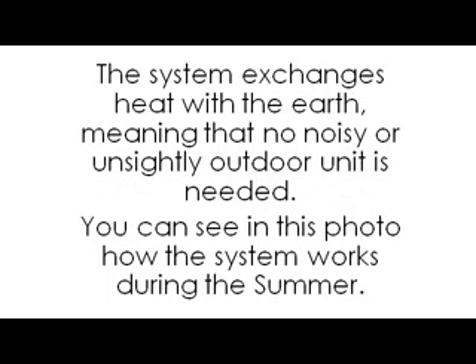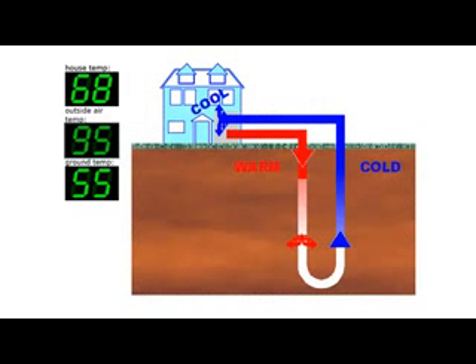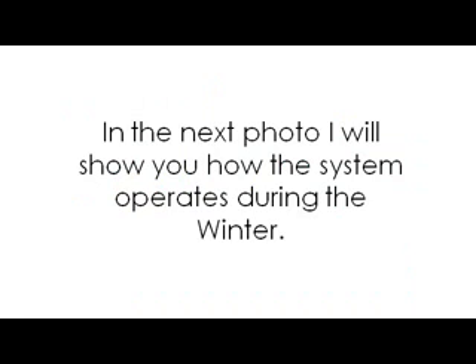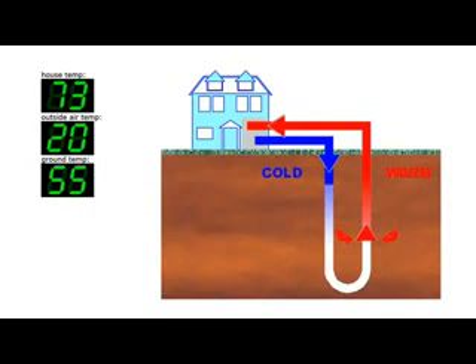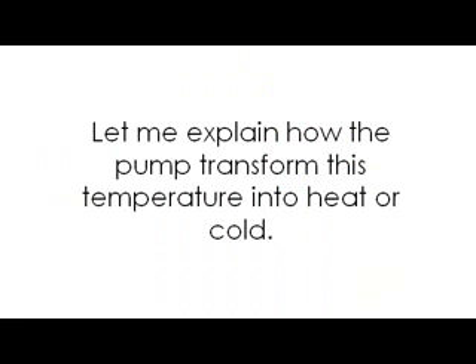You can see in this photo how the system works during the summer. The house temperature is 68 degrees Fahrenheit, outside air temp is 95 degrees, and the ground temp is only 55 degrees, which is much lower than the air temperature. In the next photo, I will show you how the system operates during the winter. The house temp is 73 degrees Fahrenheit, outside air temp is 20 degrees, and ground temp 55 degrees. Let me explain how the pump transforms this temperature into heat or cold.